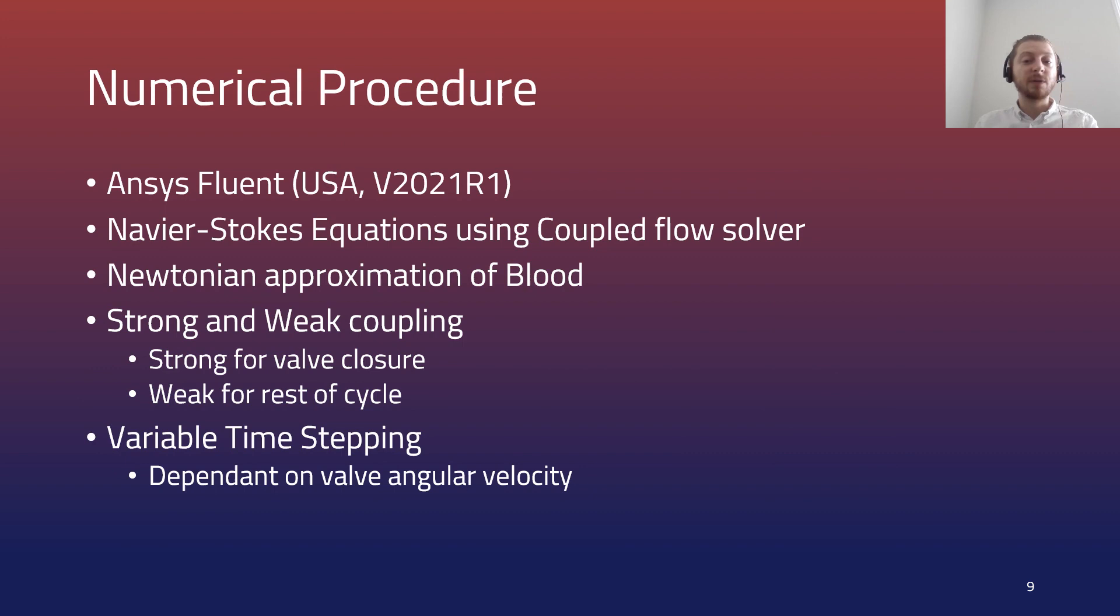ANSYS Fluent was used to solve the Navier-Stokes equations for a Newtonian approximation of blood using the coupled flow solver. A fully implicit strong coupling solution algorithm was employed during instantaneous valve opening and closing to maximize the computational accuracy at this time, whilst a weak coupling algorithm was employed for all other cycle stages to maximize the computational efficiency during that time.